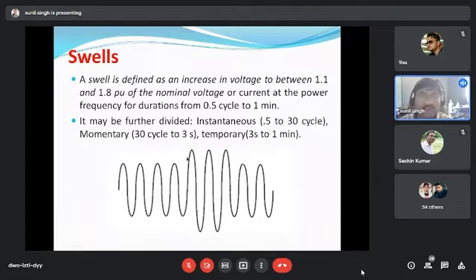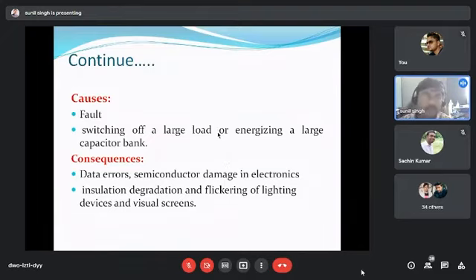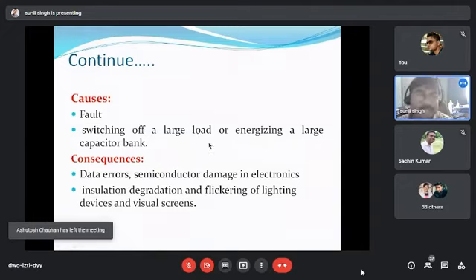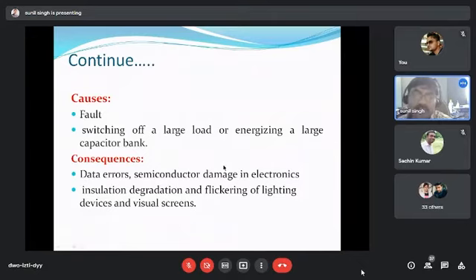The swell is an increment of the voltage greater than 1.1 per unit for a duration of 0.5 cycle to 1 minute. Again, the cause of swells is also fault, and also switching off a large load or energizing a large capacitor. Now integration of distributed generators or distributed generation in the grid is also a cause, because sometimes if we shut down that distributed generation, then suddenly our voltage will shoot up. The consequences of this high voltage for a shorter duration are data errors, semiconductor damage in electronic devices, insulation degradation, and flickering of lighting devices and visual screens.